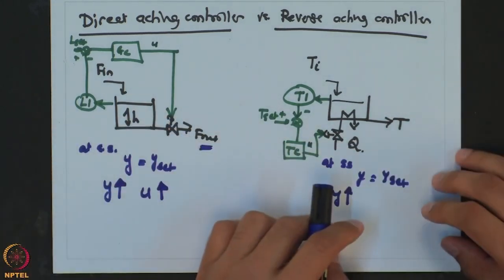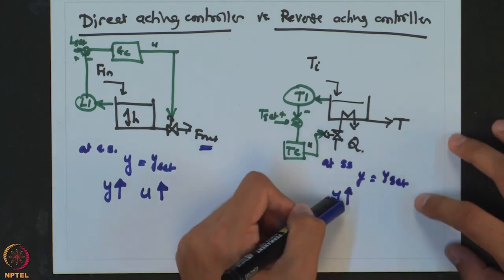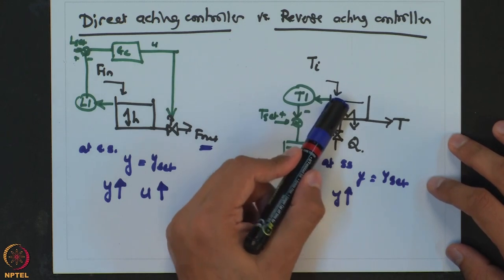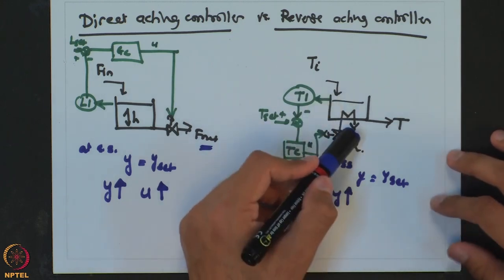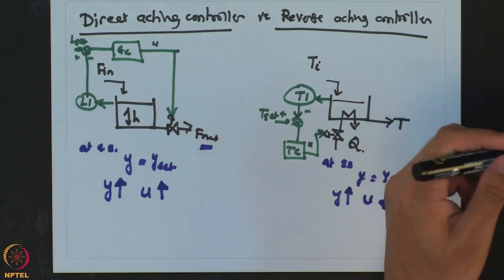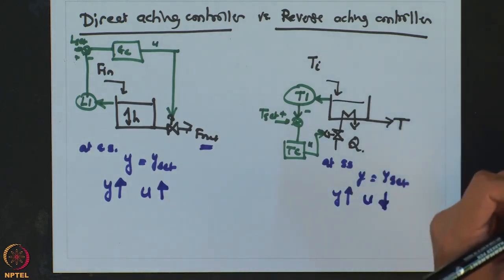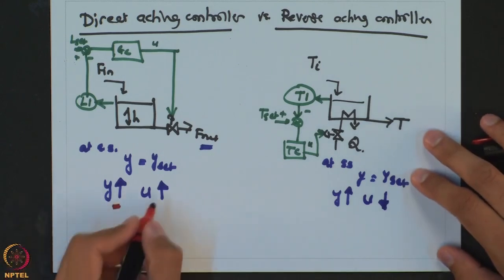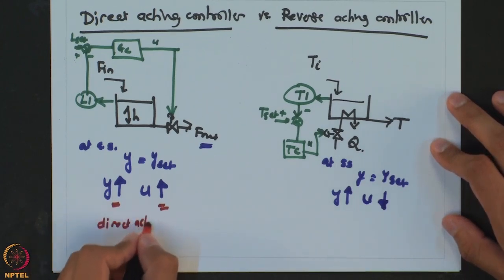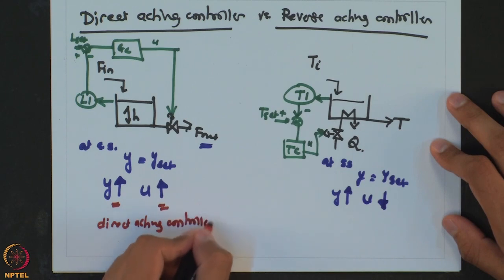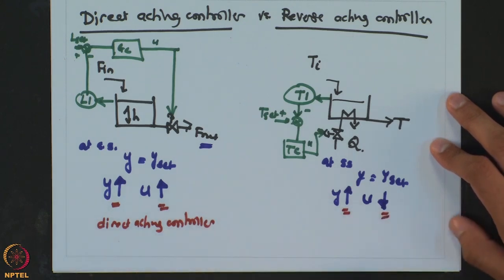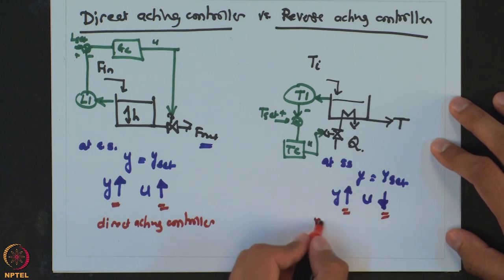Now look at the stirred tank heater case. If Y increases beyond the set point, the temperature inside the tank is above the desired value. What should the controller do? It should cut down on the heating duties applied to the system — the controller output should decrease. So you can notice the difference: in the level control case, an increase in input causes an increase in controller output, therefore it is known as a direct acting controller. In the stirred tank heater case, an increase in input causes a decrease in controller output, therefore it is known as a reverse acting controller.